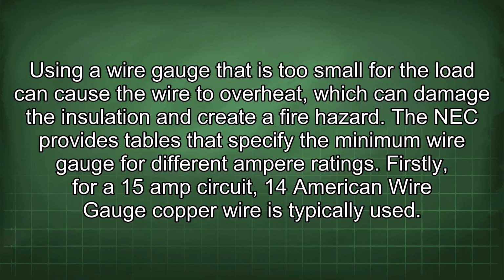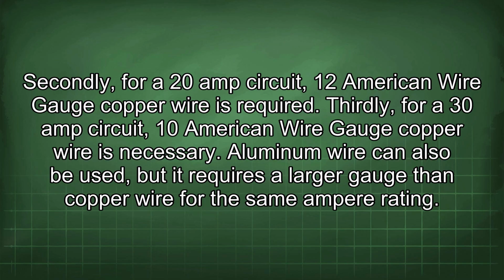The NEC provides tables that specify the minimum wire gauge for different ampere ratings. Firstly, for a 15 amp circuit, 14 American wire gauge copper wire is typically used. Secondly, for a 20 amp circuit, 12 American wire gauge copper wire is required. Thirdly, for a 30 amp circuit, 10 American wire gauge copper wire is necessary.